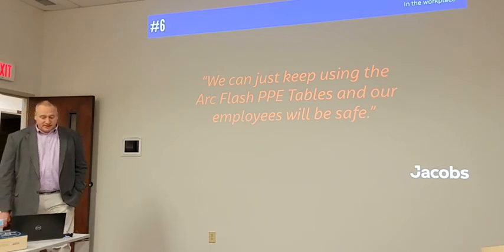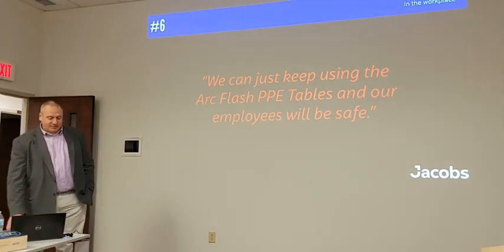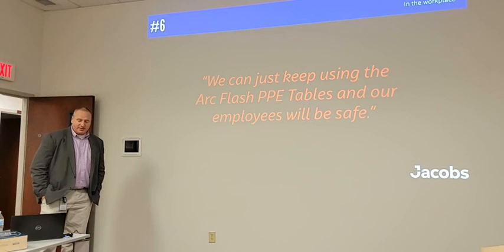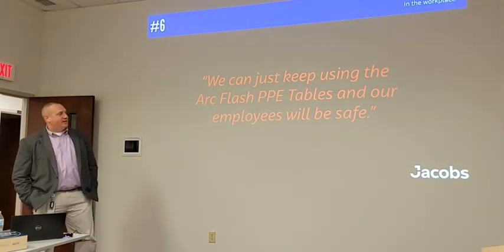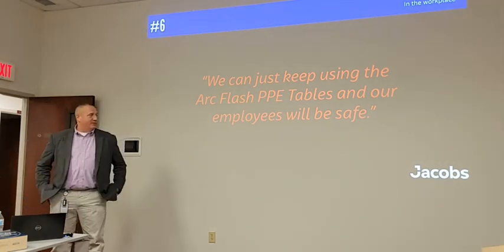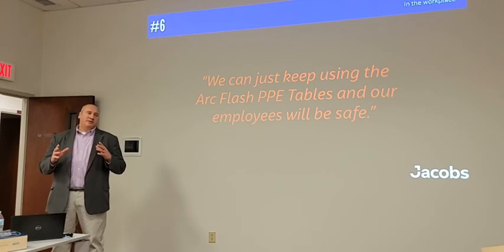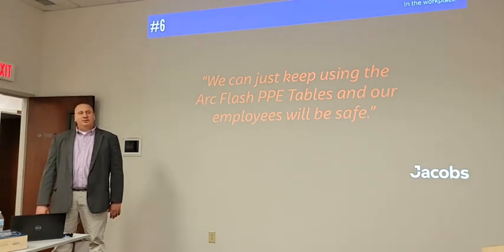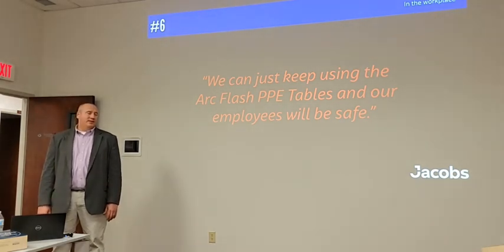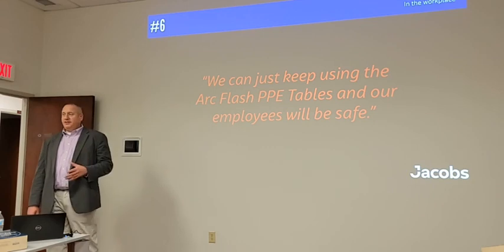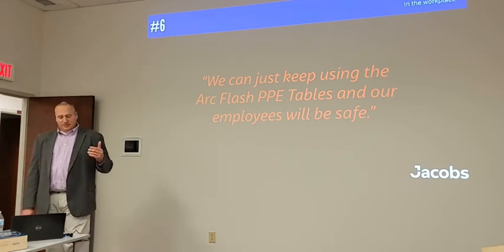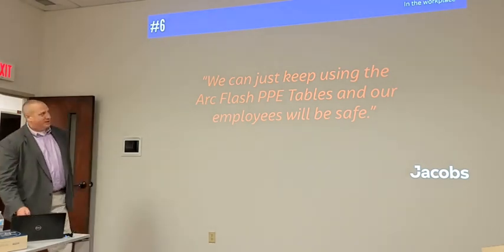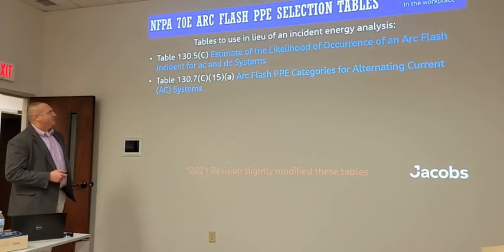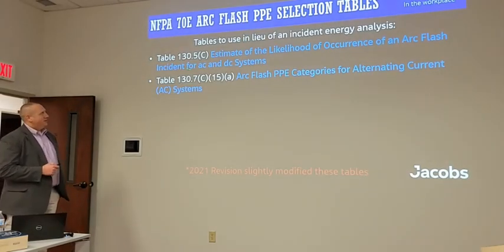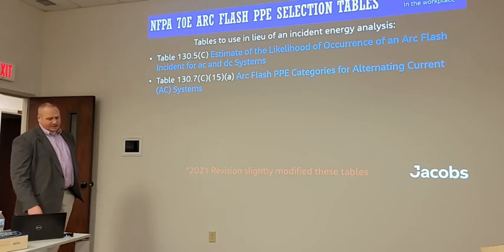The next one is that we can just keep using the arc flash PPE tables and our employees will be safe. And if you're familiar with the 70E, the first option is to do the arc flash analysis, where you actually have a calculated calories per centimeter squared incident energy rating. In lieu of doing that calculation, if it hasn't been done, they've got these tables that you can reference that'll give you some guidance on what PPE to use. And the first table is the 130.5C, and that's the likelihood of occurrence.